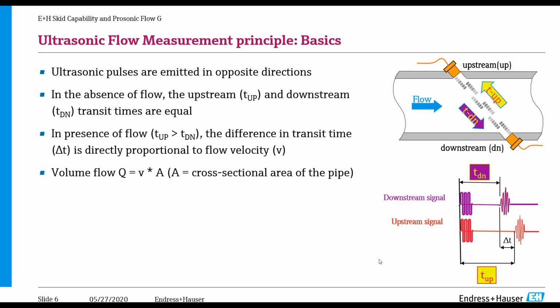These transducers are going to create and receive ultrasonic pulses. You see that they're set at an angle. When a pulse is sent with the flow, it has a certain time to cross. We measure that, and then we do this in the reverse direction, so it's going against the flow, and we measure that time. What happens is the ultrasonic signal is accelerated with the flow and decelerated against the flow. So we get a time difference, and that time difference is proportional to the flow rate in the pipe. Obviously, we just see one set of transducers here.